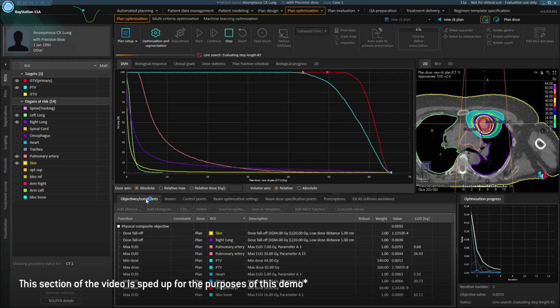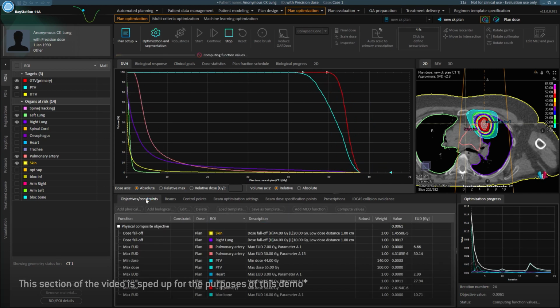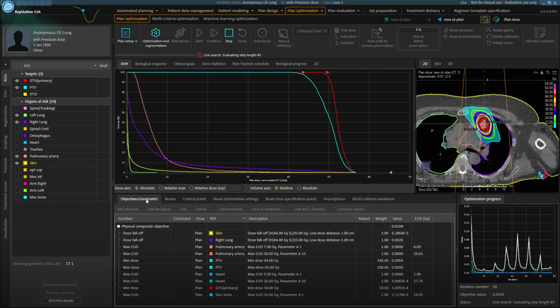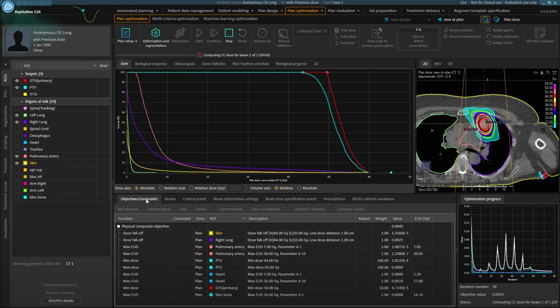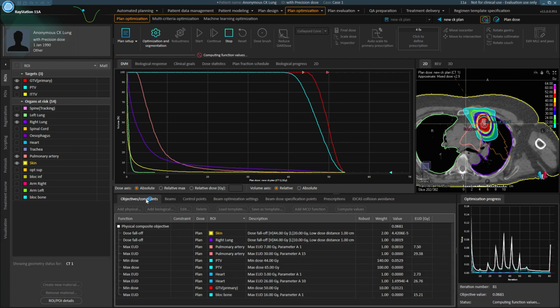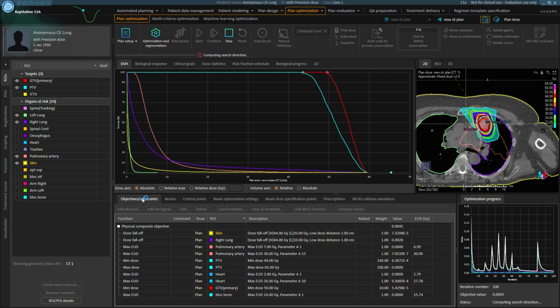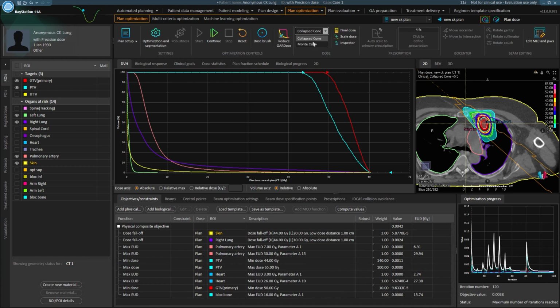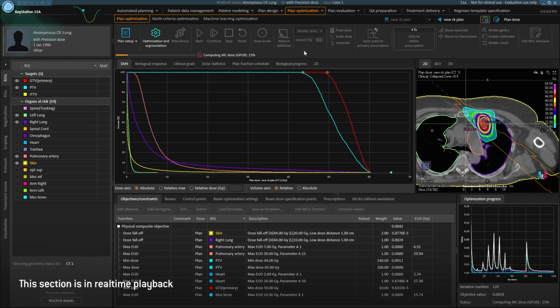Optimization and dose calculation speed is one of the main priorities for research. For optimization of Cyberknife plans, our proven optimization algorithm has been extended with support to choose the optimal node positions and beam angles for each individual patient. Segment weight optimization is performed for all collimation types. And for MLC plans, this is combined with the powerful direct machine parameter optimization of the leaf positions. We support collapsed cone and Monte Carlo dose computations, both for computing final dose and as intermediate dose during optimization.